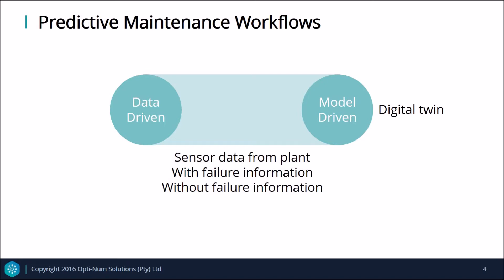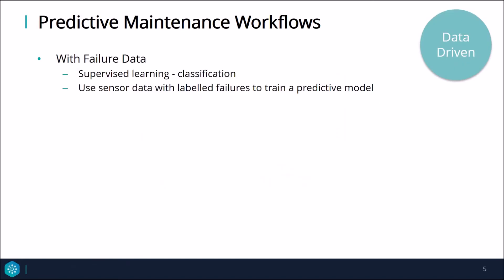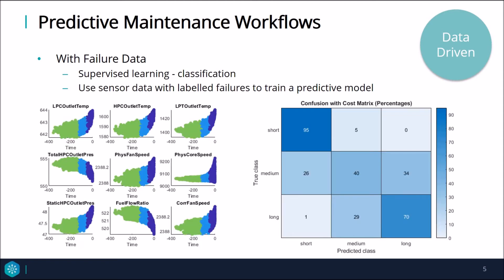The first use case is when we have failure data from our plant, flagged with either run-to-failure information or with unexpected failures flagged in our historical database. In this case, we can use a supervised machine learning approach, like a classification algorithm, for identifying when a sensor is in a particular state. In the example here, we have run-to-failure sensor data from turbofan engines. The data has been flagged to indicate a long, medium, or short time until maintenance needs to occur. A classification algorithm is trained with this data, and the time to maintenance is set as the output. In production, this system would generate a warning when there is a medium duration until failure, or an alert when sensor data indicates a short time until failure.